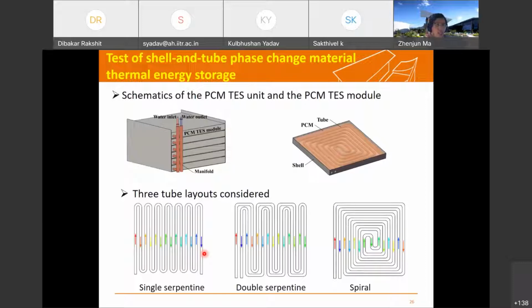We tested a shell and tube phase change material storage. Our design is based on a modular design. This is the single module, with an inlet and outlet section. If you want to increase the capacity of the thermal energy storage, you can put multiple units together to get different capacities.